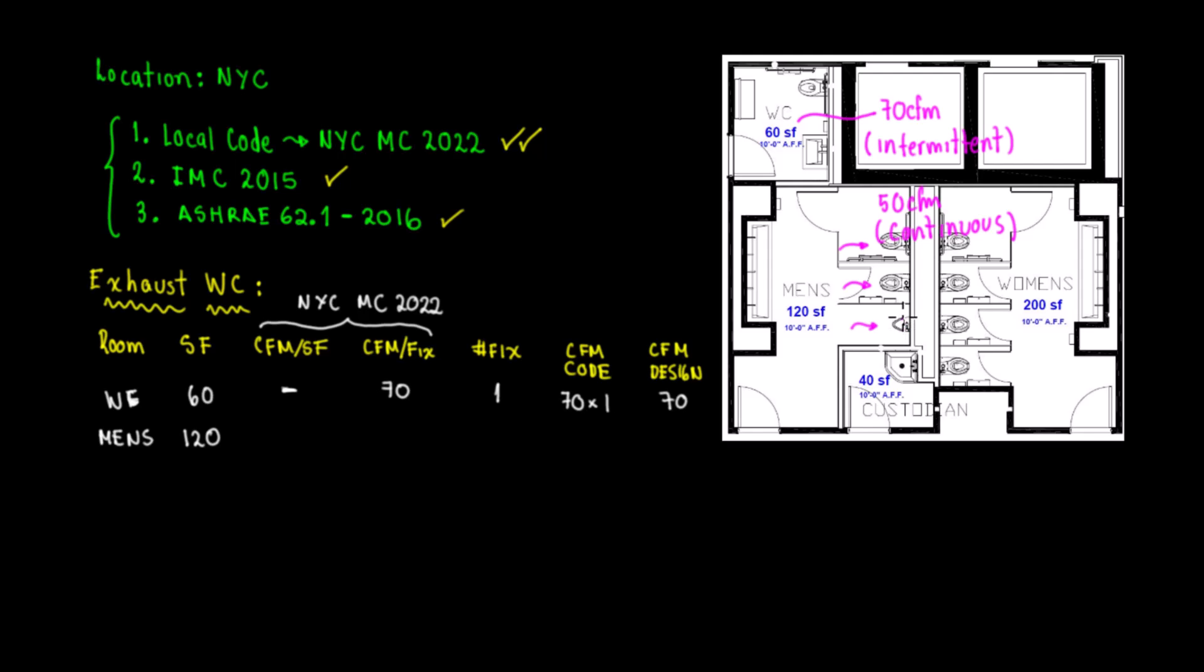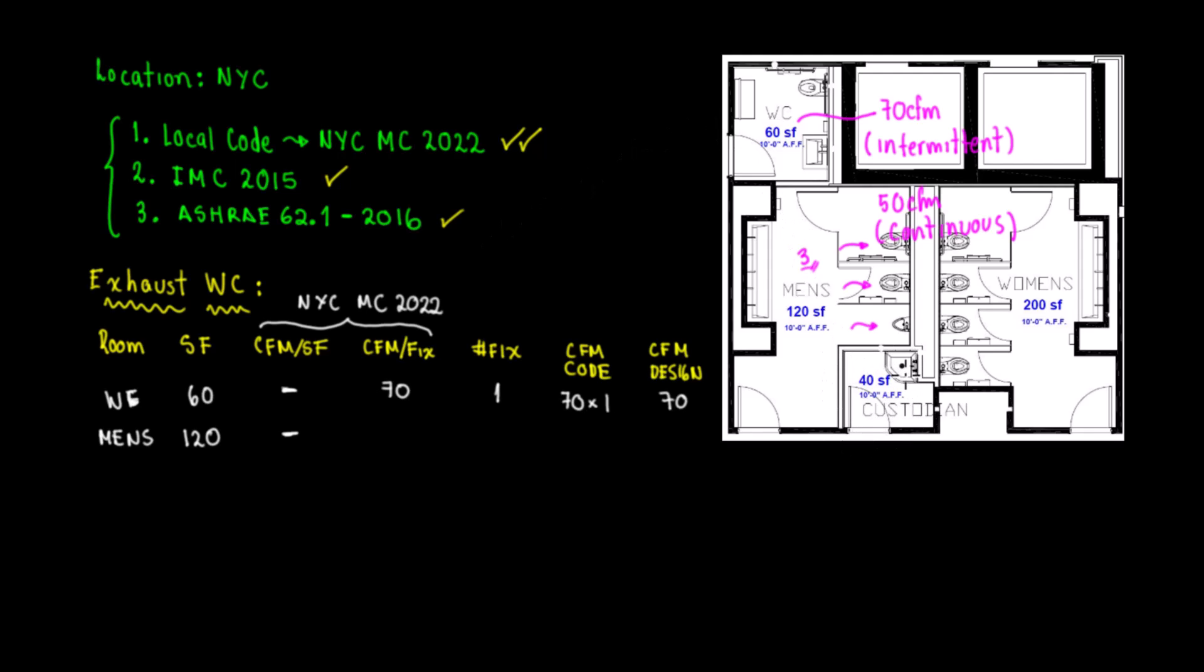Fixture is the water closet, toilet, and urinal. We don't have any showers. How many fixtures do we have? One, two, three, so we're going to put three fixtures. CFM per square feet - code doesn't say that, so we don't want to get confused. The New York City Mechanical Code 2022 indicates that CFM per square feet is for the custodian or janitor's closet.